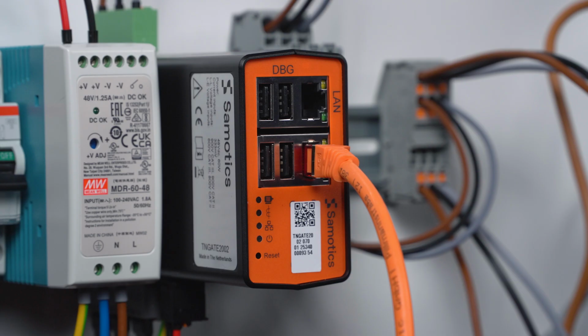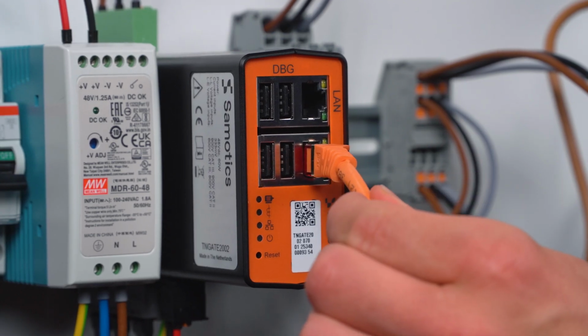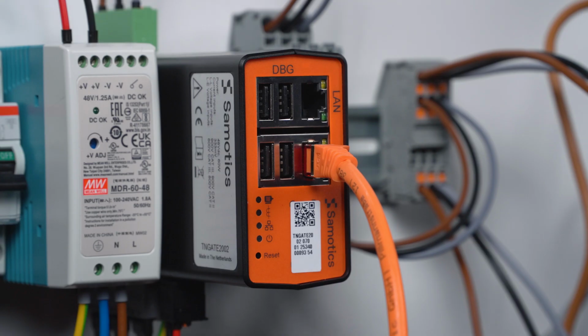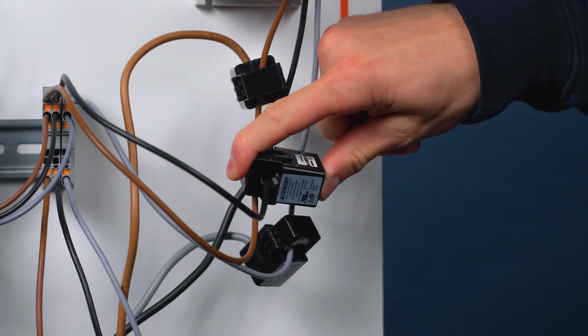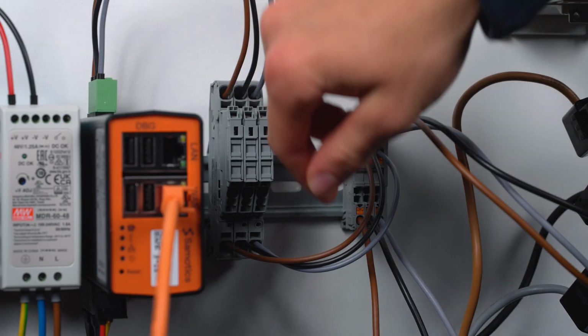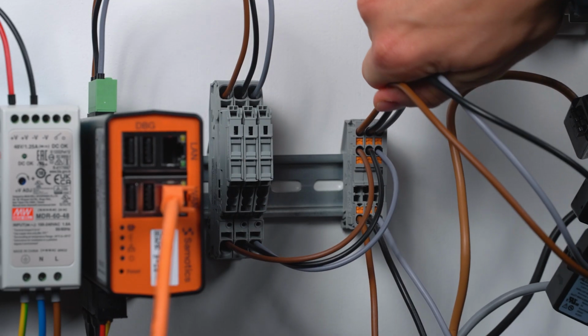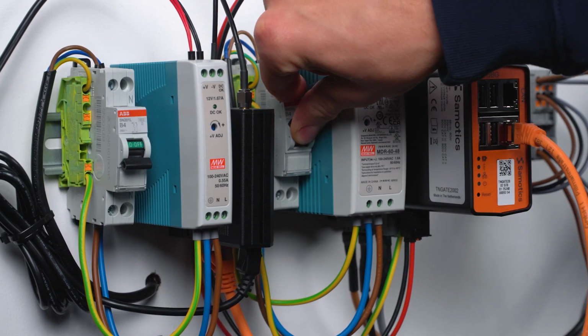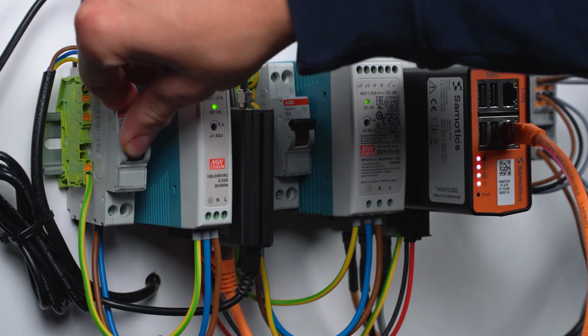Before powering up the SAM4 installation, double-check that the Ethernet cables are correctly plugged into the devices, that all current transformers are properly closed, and that the voltage wires are correctly connected. To power up the system, connect the power supply to the power grid.